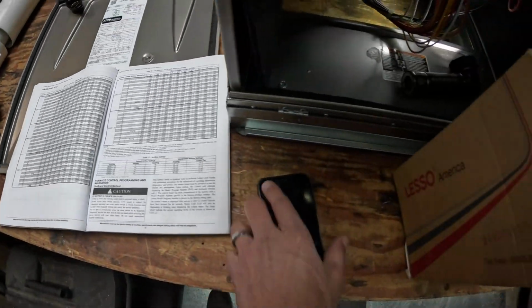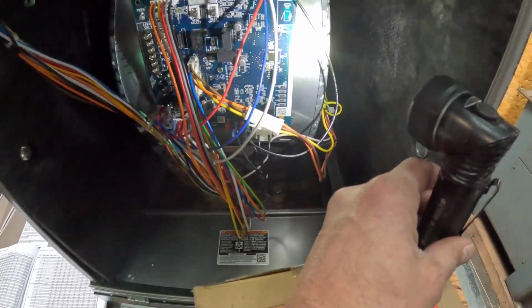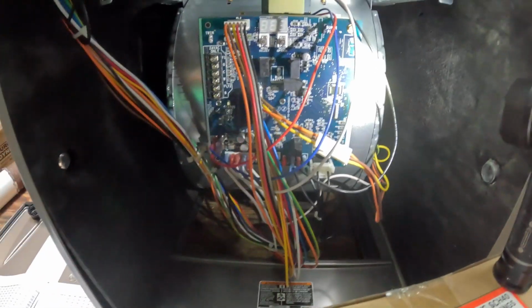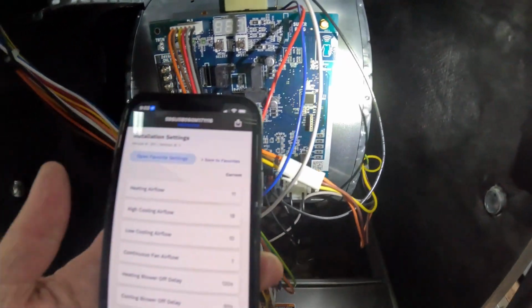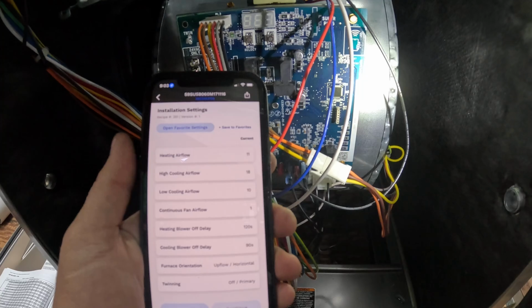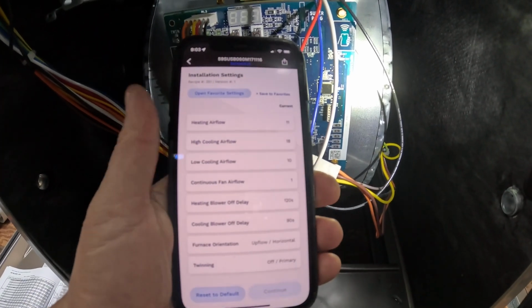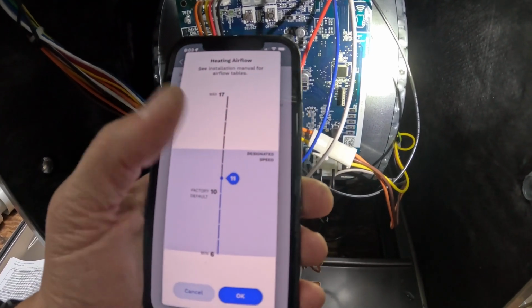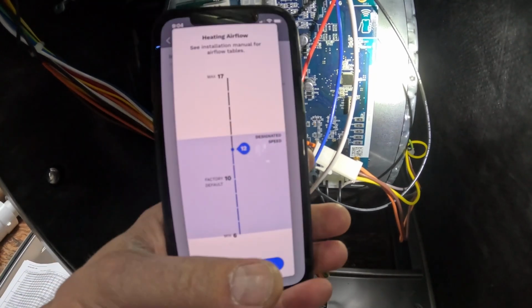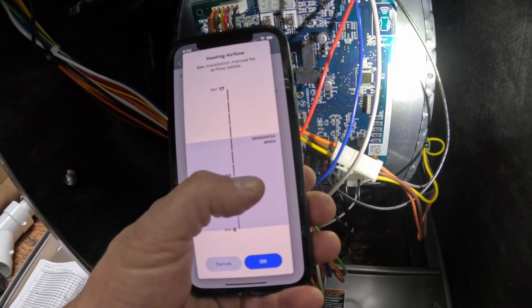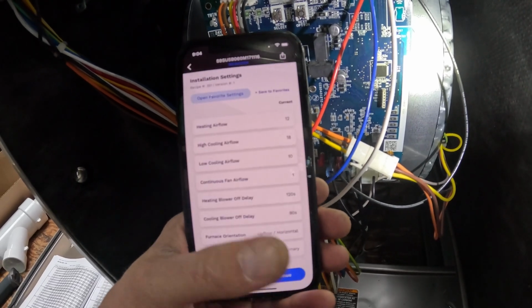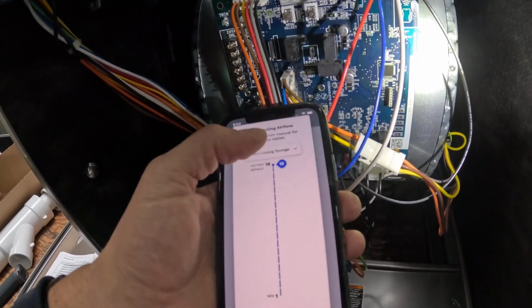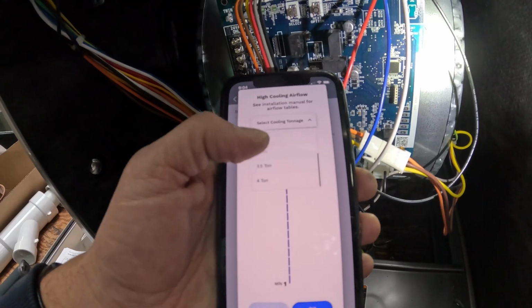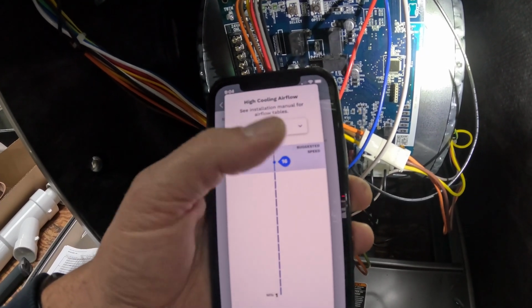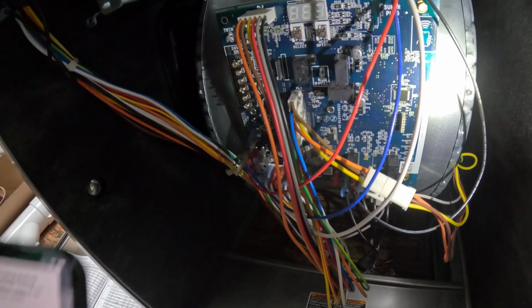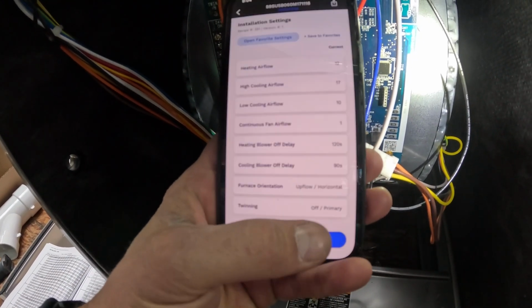To be able to do that, we're going to go back over to the NFC board here, and we're going to be holding our phone, and you do want to keep it slightly close, especially after you finish. You want to hold this phone pretty close to make sure it locks in. For the heating settings, we're actually going to move up to a 12. We can move this slider up and down right there, and we're going to say OK. For the cooling airflow, we're first going to select tonnage, and we're going to select 4-ton, and I'm going to move it to 17. I'm going to select OK for that.